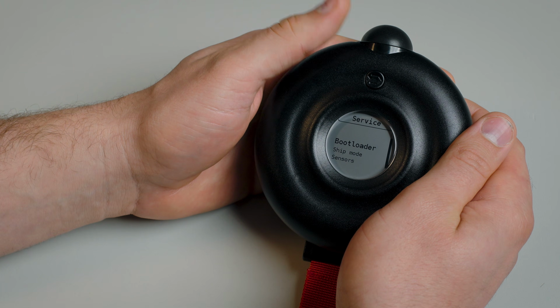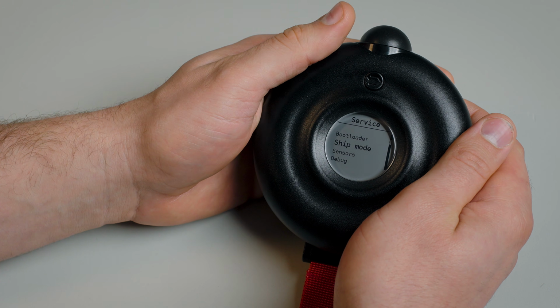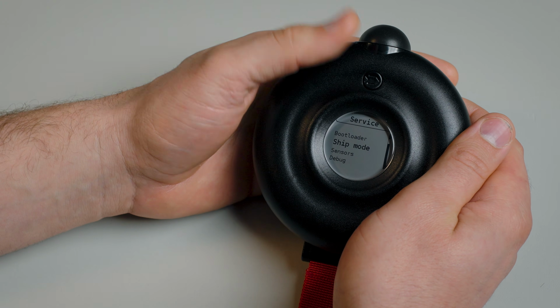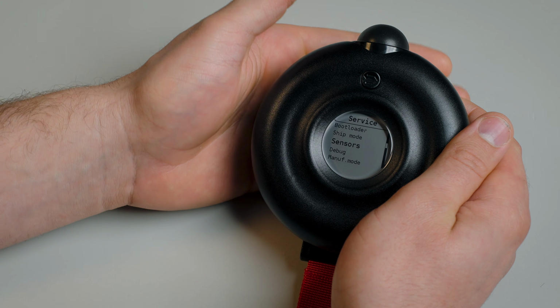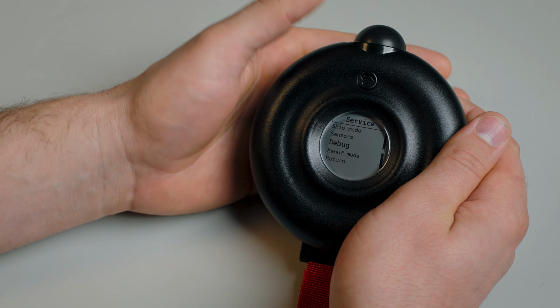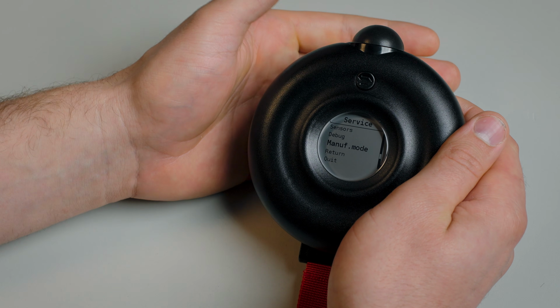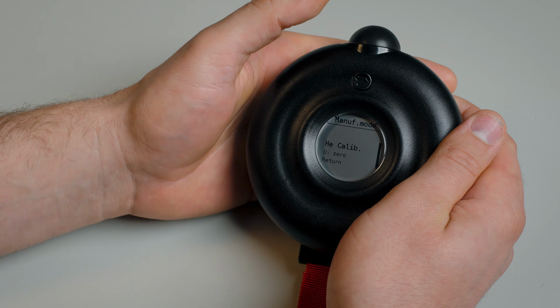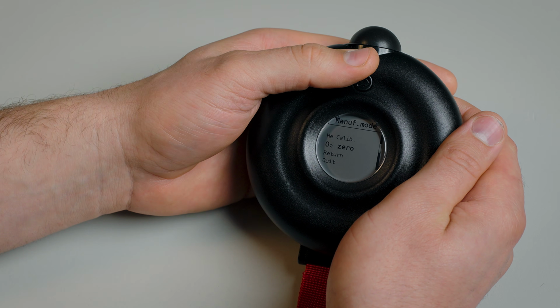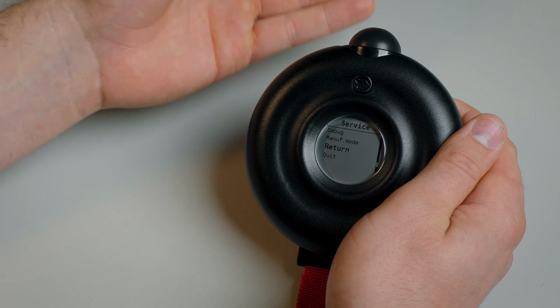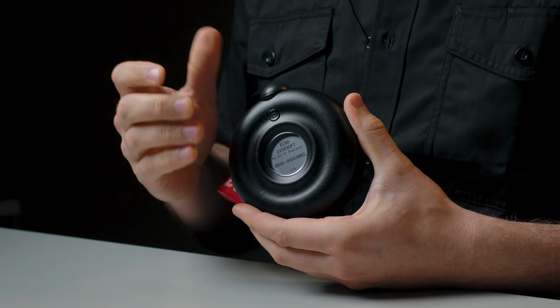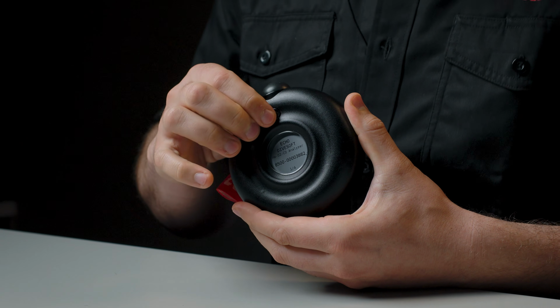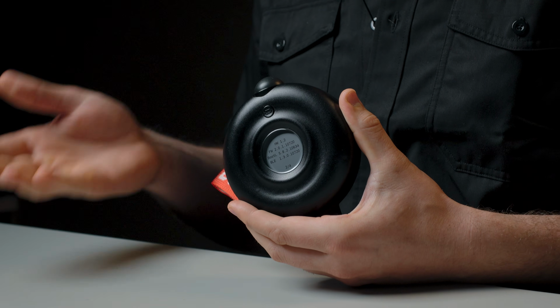In the service menu, you can enter bootloader mode when you want to update your device manually, and ship mode when your device is turned off for a while and you want it to stay turned off. Here you can see the raw readings from your sensors. Then you can enter debug mode and manufacturer mode, where you can, for example, calibrate the helium sensors or zero your O2 sensors. From here, you can return to your previous menu or again, go back into the main screen. And the last item is the About section. Here you can find the serial number of your analyzer and, for example, the hardware and firmware versions.